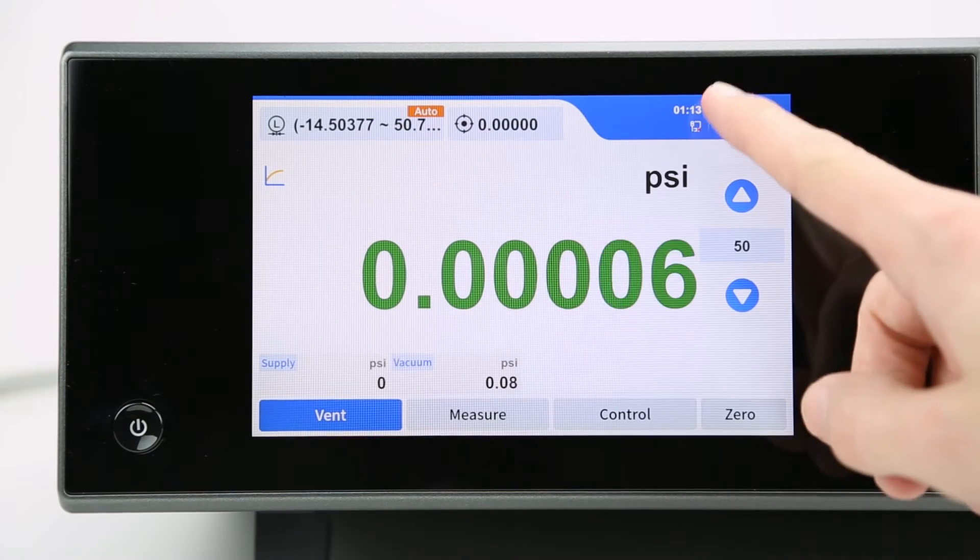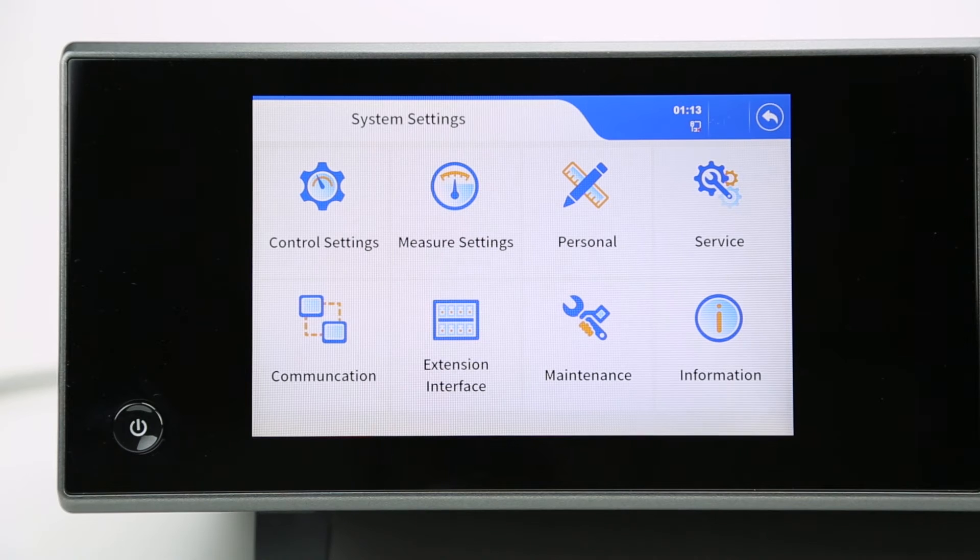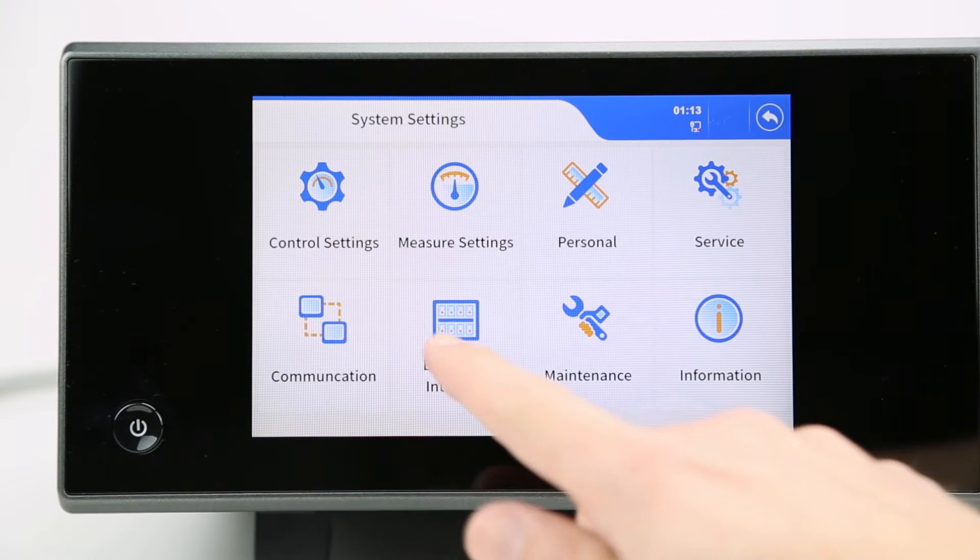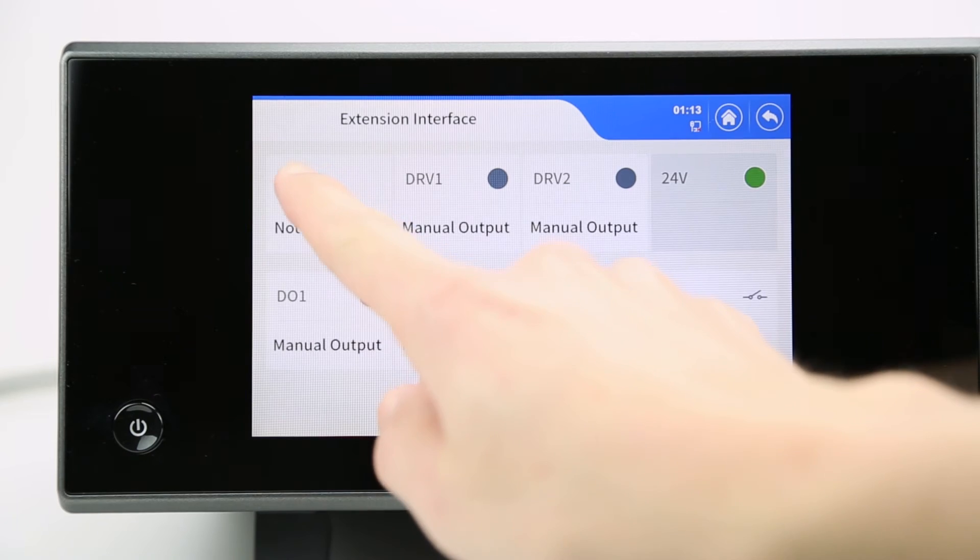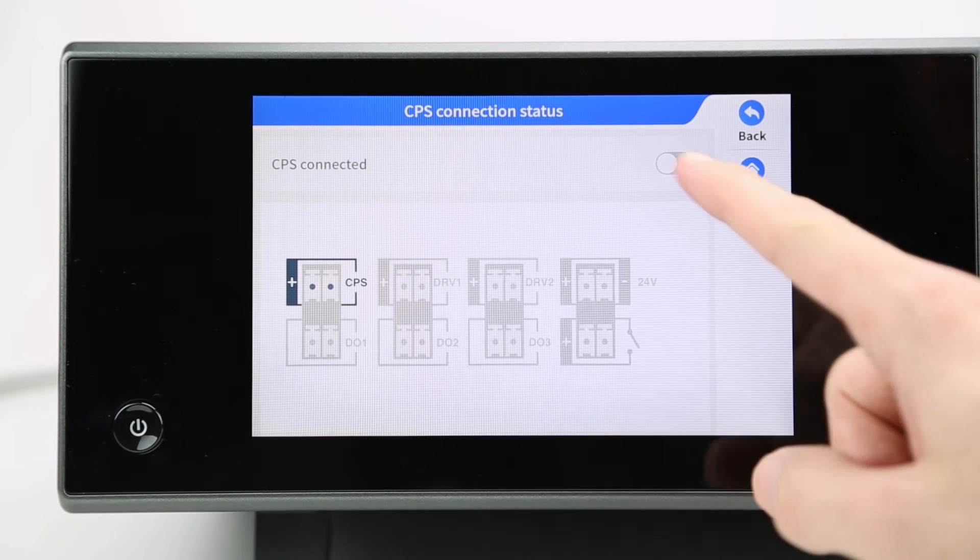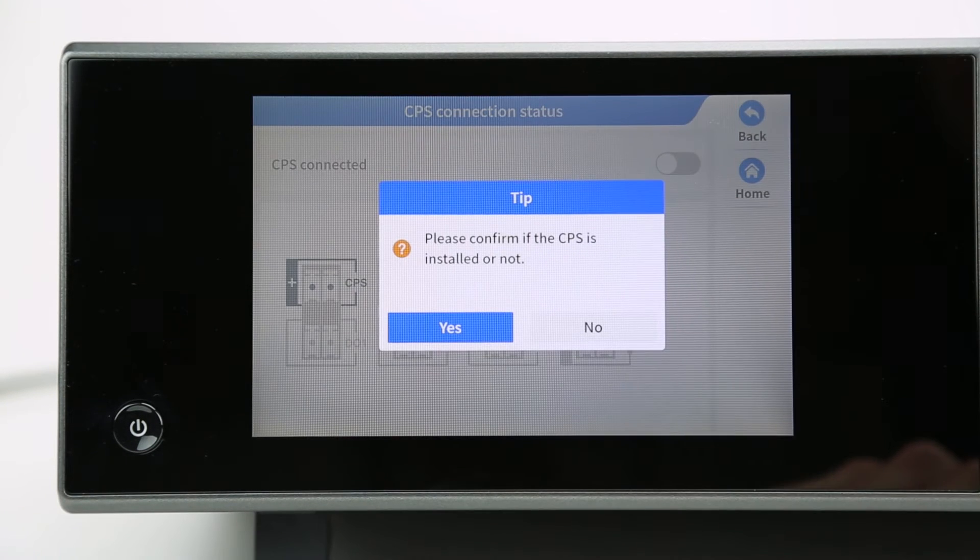To ensure the CPS is active, select the settings icon from the main screen of the controller, then select extension interface. From here, select the CPS option to toggle it on, where you'll be asked to confirm that the CPS is installed.